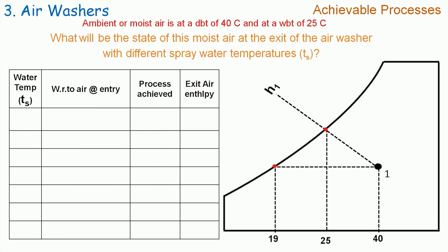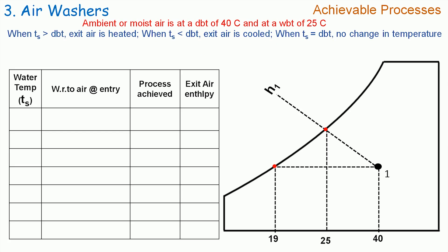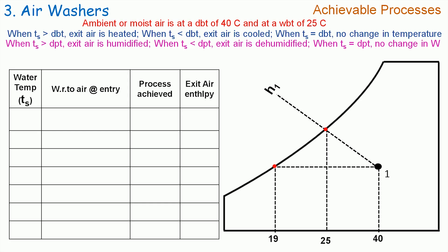Let me first explain how the spray water temperature and the psychrometric properties of the moist air are related. Whenever the spray water temperature TS is greater than the dry bulb temperature, then the exit air is heated. Whenever TS is less than the dry bulb temperature, then the exit air is cooled. Whenever TS is equal to DBT, then there is no change in the temperature of the moist air. Similarly, whenever TS is less than dew point temperature, then exit air is dehumidified. And whenever TS is equal to dew point temperature, then there is no change in the specific humidity of the moist air.